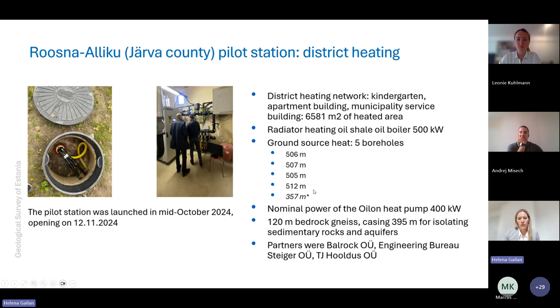We actually drilled 5 boreholes there, but the 5th one was terminated due to pressure problems. The first year results showed an average heat production of 74 megawatt hours per month, with heat power at 110 kilowatts. So we see the installed capacity is a bit overestimated. We installed a 400 kilowatt heat pump, but the actual usage is only 110 kilowatts, and the coefficient of performance is rather low, like 3.2.